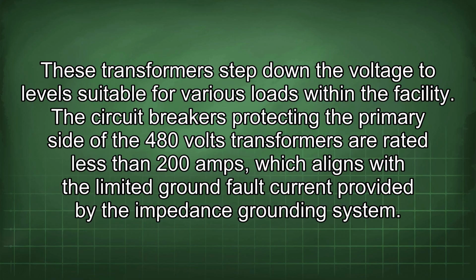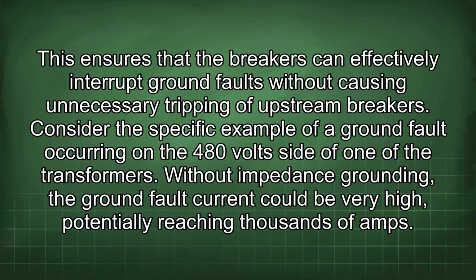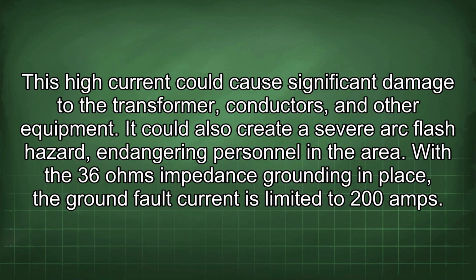The circuit breakers protecting the primary side of the 480 volts transformers are rated less than 200 amps, which aligns with the limited ground fault current provided by the impedance grounding system. This ensures that the breakers can effectively interrupt ground faults without causing unnecessary tripping of upstream breakers. Consider the specific example of a ground fault occurring on the 480-volt side of one of the transformers. Without impedance grounding, the ground fault current could be very high, potentially reaching thousands of amps. This high current could cause significant damage to the transformer, conductors, and other equipment. It could also create a severe arc flash hazard, endangering personnel in the area.